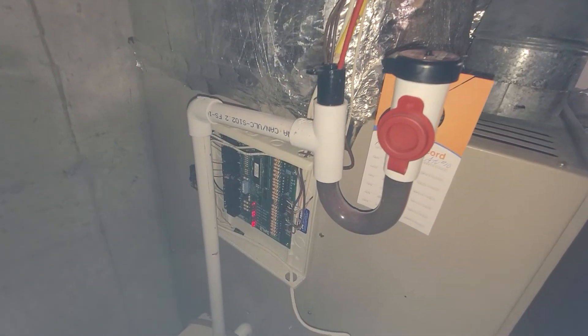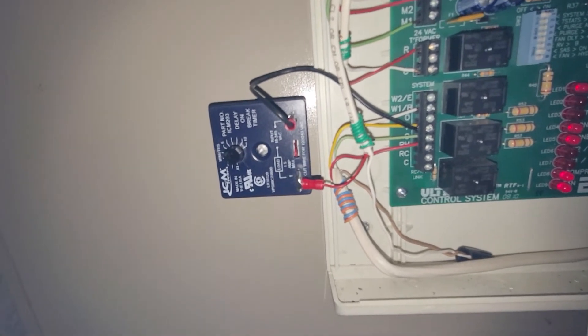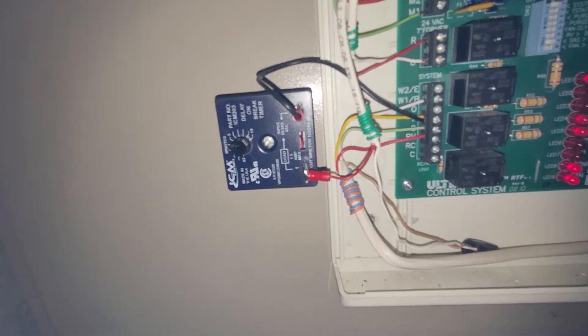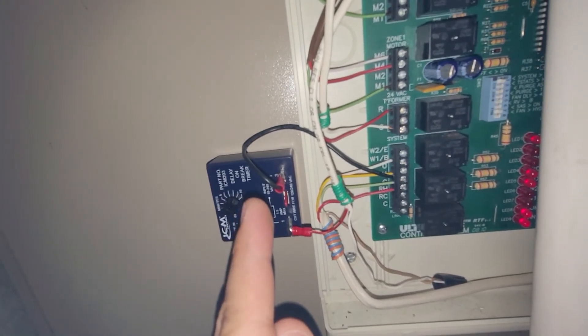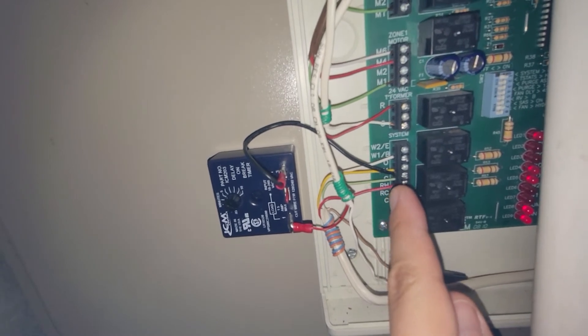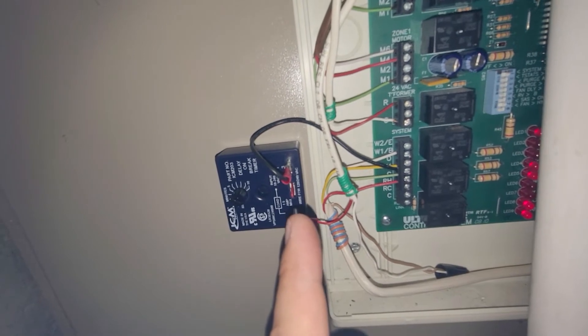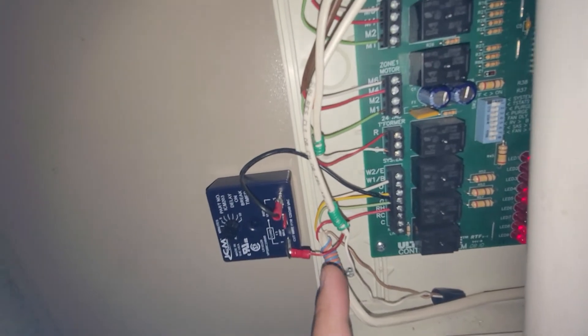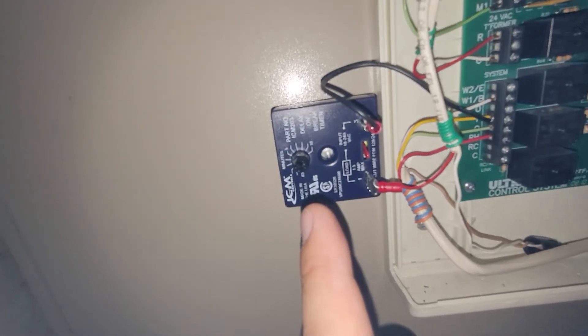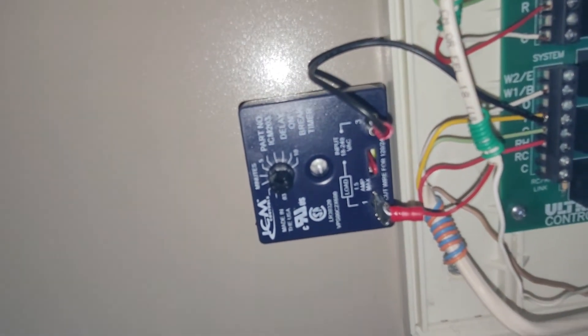So what I did is I got one of these — it is an ICM203, a delay-on-break timer. I basically connected it to the supply on this side. The yellow terminal is what calls for cooling into the system, and this is specifically for the compressor contactor. Then this side is what goes to the contactor, this red wire. I've set it — I don't know if you can see it that well — but I've set it to five minutes.